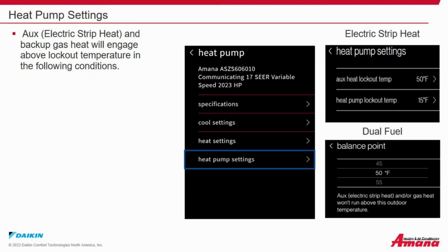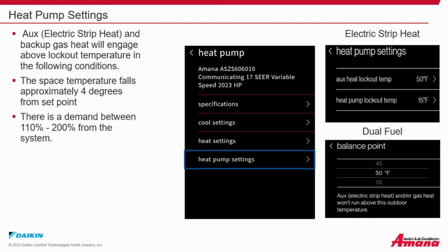The auxiliary electric heat strip and backup gas heat will engage above lockout temperature in the following conditions. If the space temperature falls approximately 4 degrees below set point, or if there is a demand of between 110% and 200% from the system.